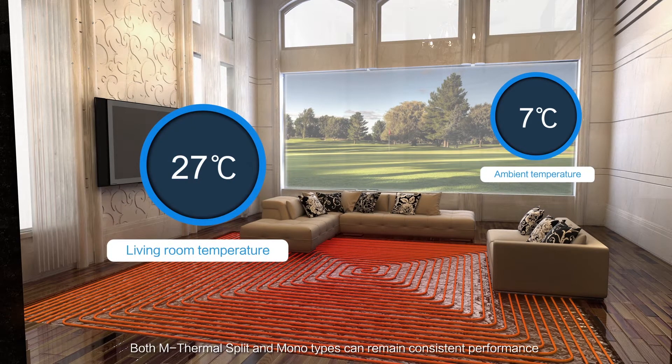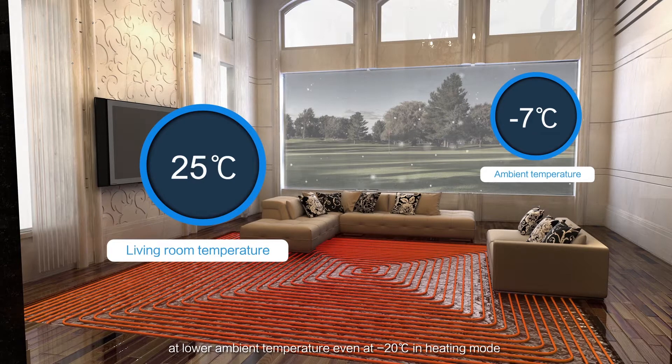Both M-Thermal Split and Mono types can maintain consistent performance at lower ambient temperatures, even at minus 20 degrees Celsius in heating mode. Heating capacity of M-Thermal Heat Pumps can remain at 80% at minus 7 degrees Celsius.